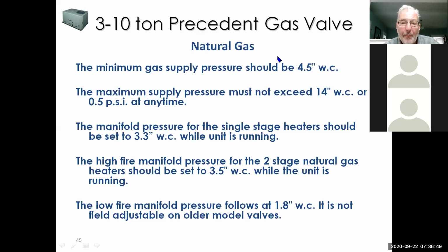So the minimum gas pressure coming into the unit needs to be 4.5 inches, while the unit's running. Maximum supply pressure, again, is 14 inches. If you get over a half a pound or 14 inches of pressure, what's going to happen is the valve may not open. So the valve is designed to open against that 14 inches. Anything over that, the valve may not open. It may lock itself up.